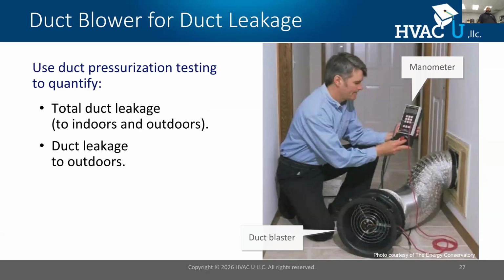Another way to evaluate for leakage. Now, how does this differ? The pressure pan test is measuring the pressure differential across the thermal boundary. It's really looking to see if the ducts are communicating with the space, all right, unacceptably with the space and outside. This is a different test for a different purpose. It still is going to evaluate duct leakage, but now we're trying to quantify duct leakage. Quantify, actually get a number. All right, so we have two tests that we do to quantify duct leakage, and one is total duct leakage, where we're looking to see how many CFM are we losing if we have a reference point? And then the other one is going to be duct leakage to outdoors.